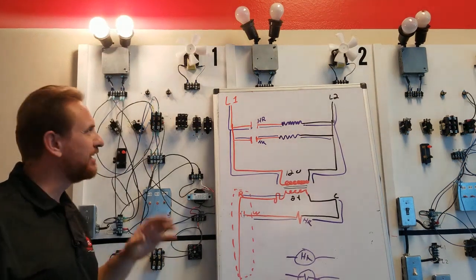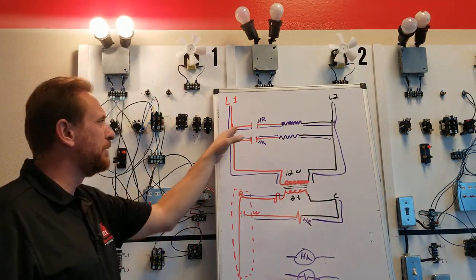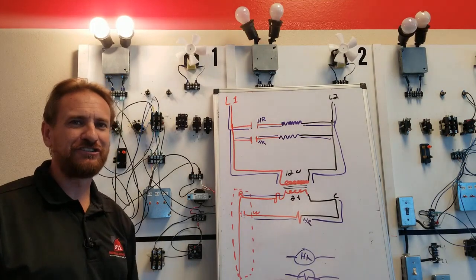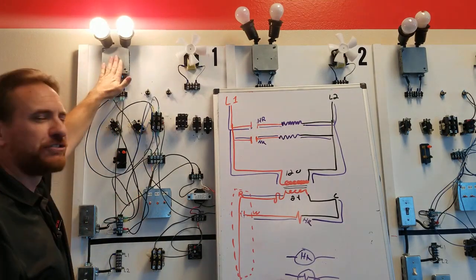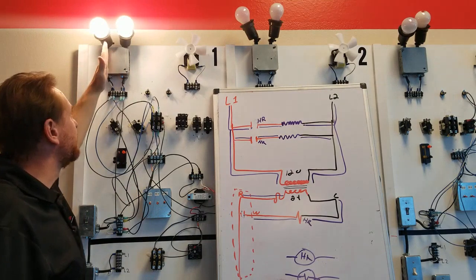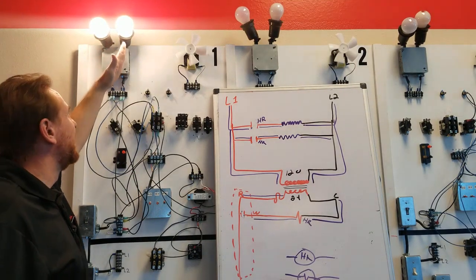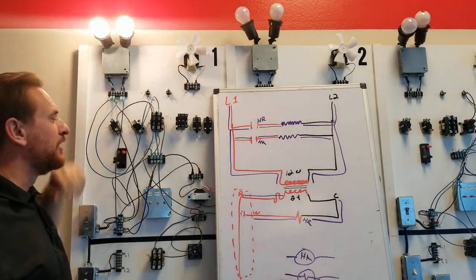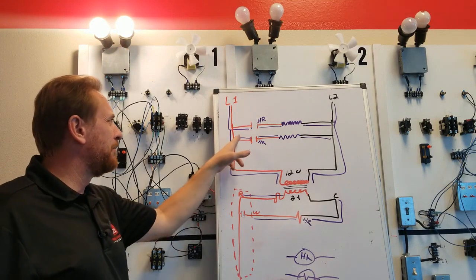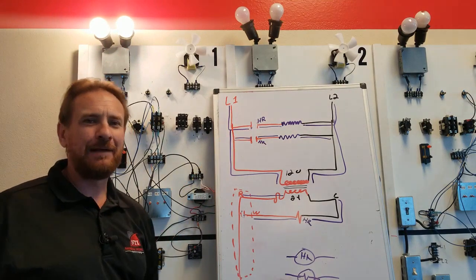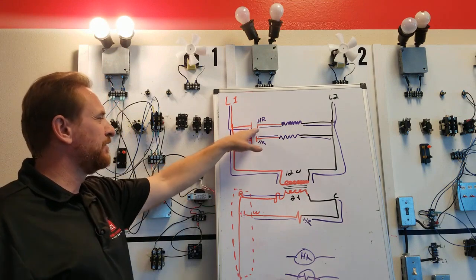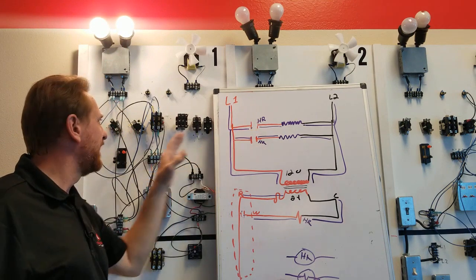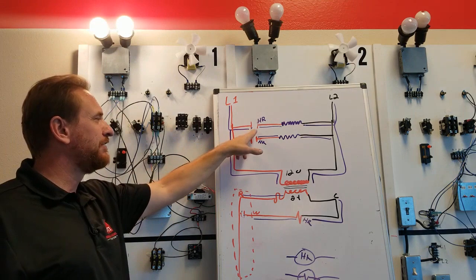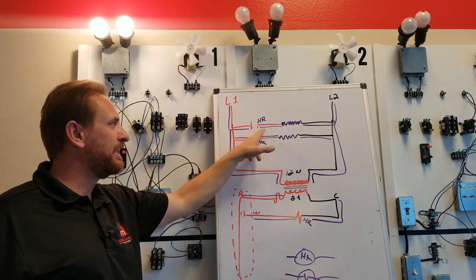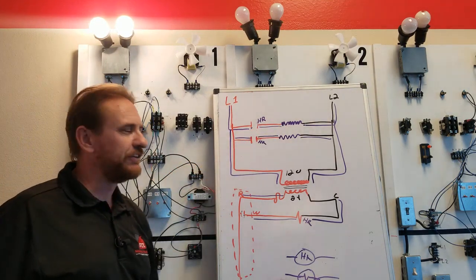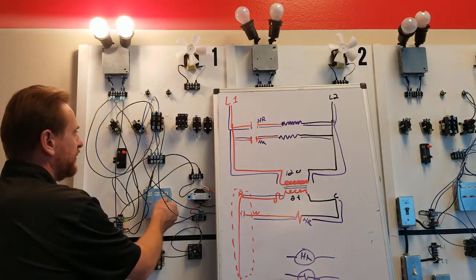Now here we just have light bulbs. I could put both these light bulbs on the same switch since they're just light bulbs, but I'm practicing as if these were electric heaters, pulling about 20 amps each. The problem is, if I put both through the same switch, that's 40 amps going to that switch. This switch can only handle about 25 amps, so pulling 40 amps through it would overload it. 20 amps is just fine.